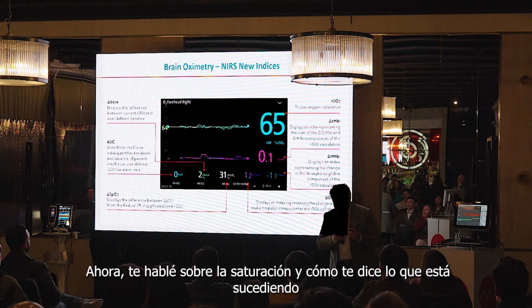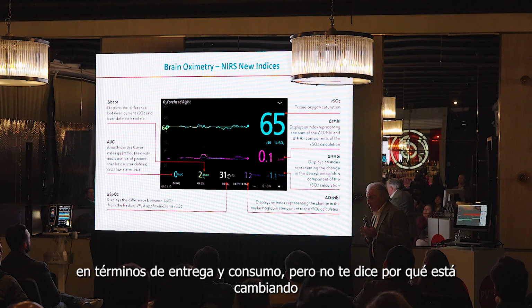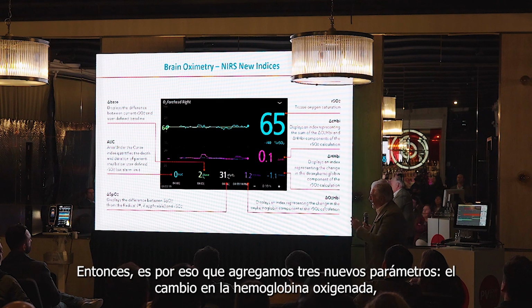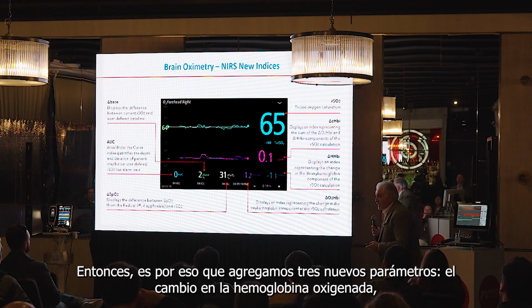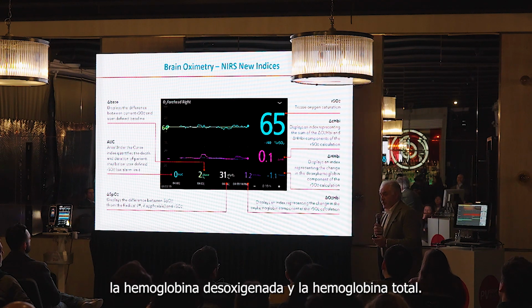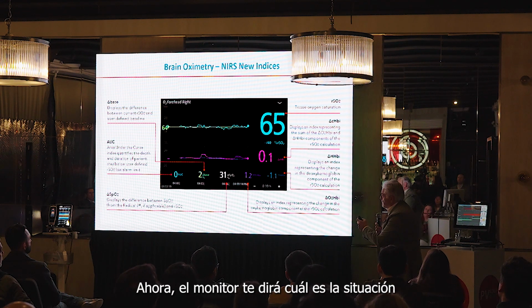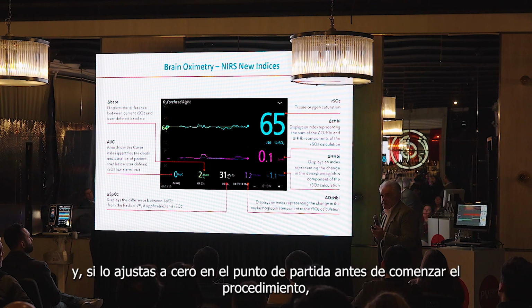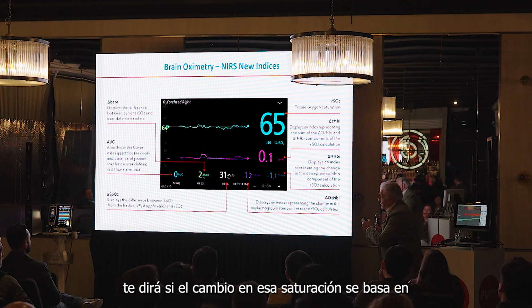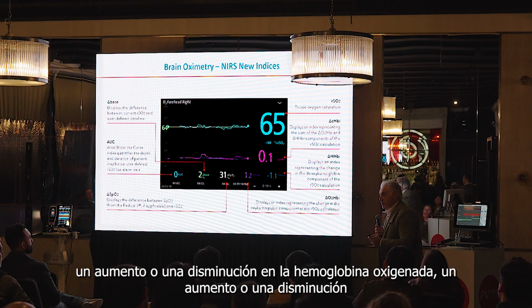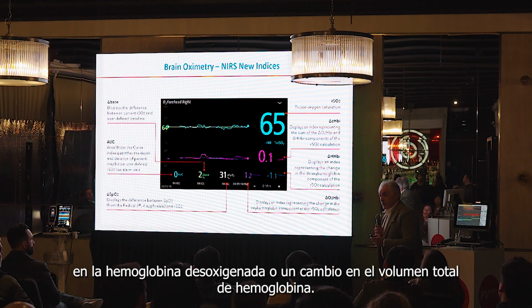Now, I told you about the saturation, that it tells you what's happening in terms of delivery and consumption, but it doesn't tell you why it's changing. Okay? So that's why we added the 3 new parameters: the change in oxygenated hemoglobin, deoxygenated hemoglobin, and total hemoglobin. So now the monitor will tell you what the saturation is, and if you zero it at baseline before you start your procedure, it will tell you the change in that saturation is based on an increase or decrease in oxygenated hemoglobin, an increase or decrease in deoxygenated hemoglobin, or a change in total hemoglobin volume.